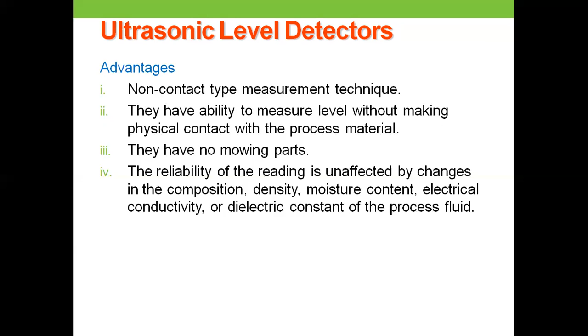Some of the advantages are that it is non-contact type, has no moving parts, and is unaffected by changes in composition, density, moisture content, dielectric constant, etc. Considering some of the limitations of these ultrasonic level sensors, temperature compensation is essential. Dirt and irregular or sloped surfaces affect the accuracy of the measurement. The ultrasonic transmitter is subject to many interferences, which affect the strength of the echo. The echo can be weak due to dispersion and absorption.